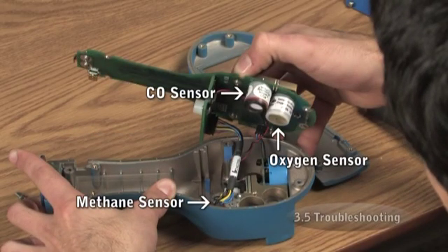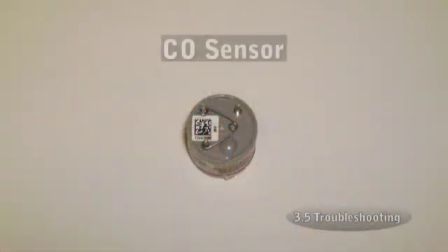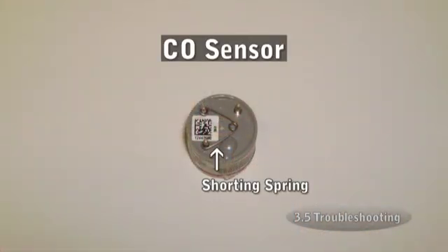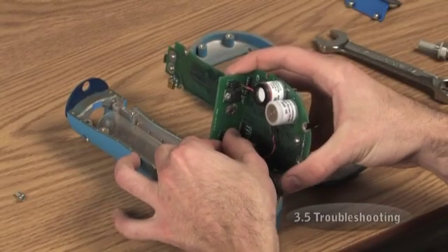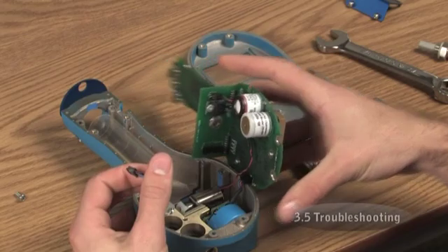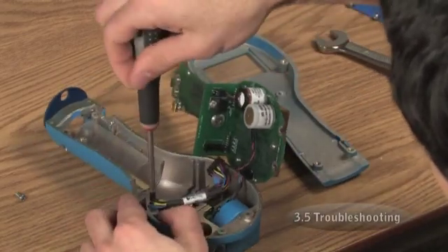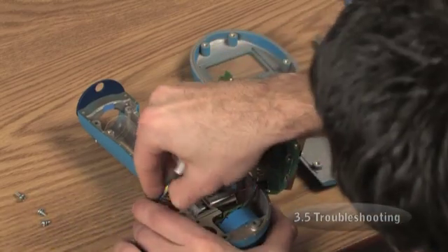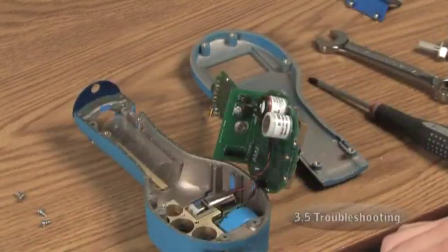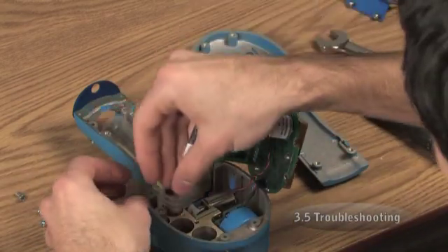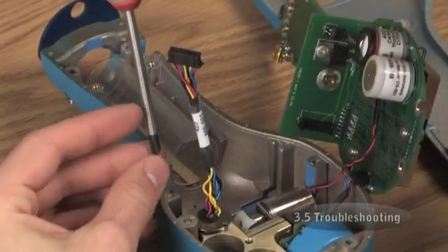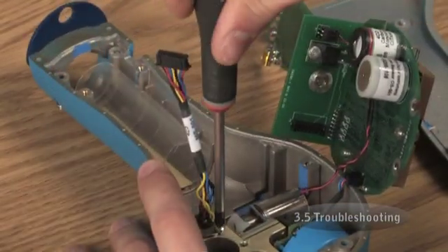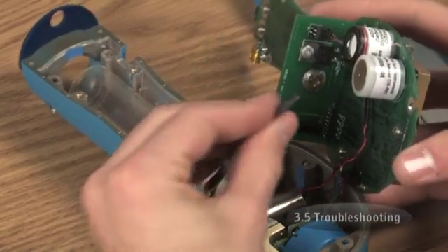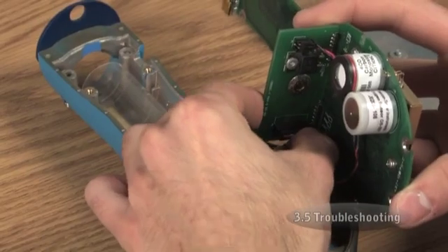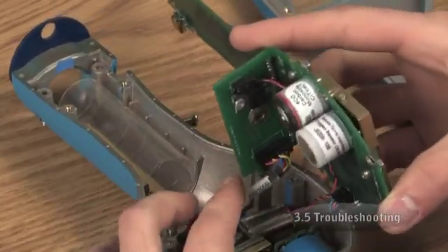Locate the sensor to be changed on the underside of the circuit board. If you are replacing the CO sensor, you will need to remove the shorting spring from the CO sensor first. To replace the methane sensor in your Explorer, unplug the old sensor and set it aside. Plug in the new sensor. Verify that the methane sensor is plugged into its socket. The socket is polarized and will only accept the methane sensor plug in the correct orientation.